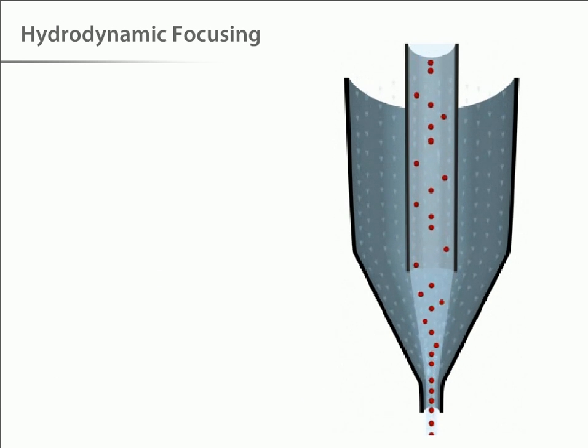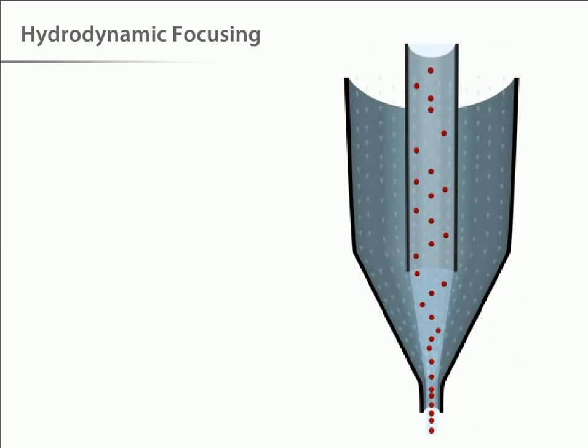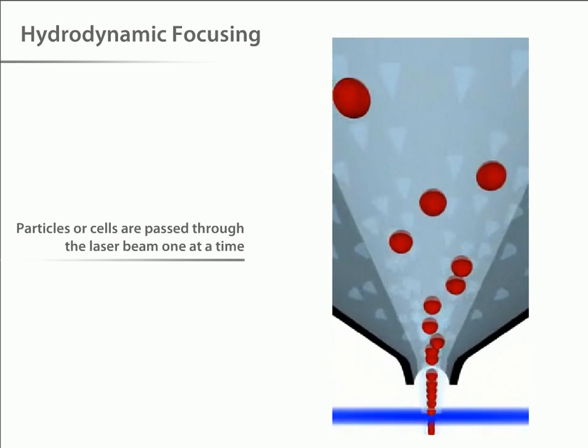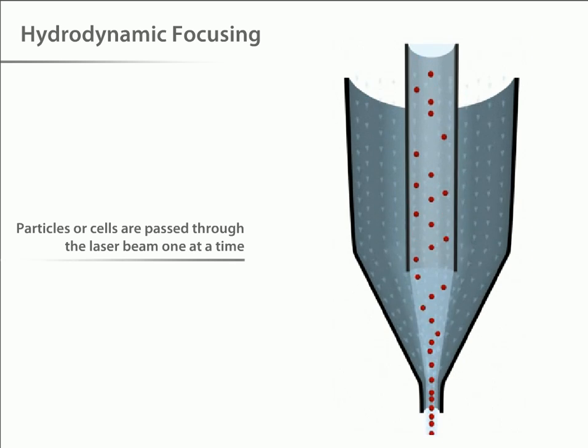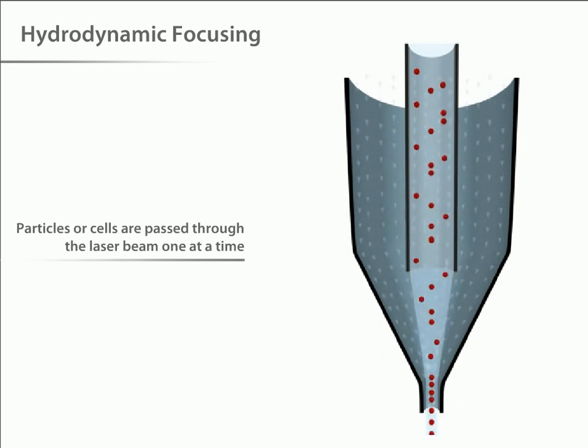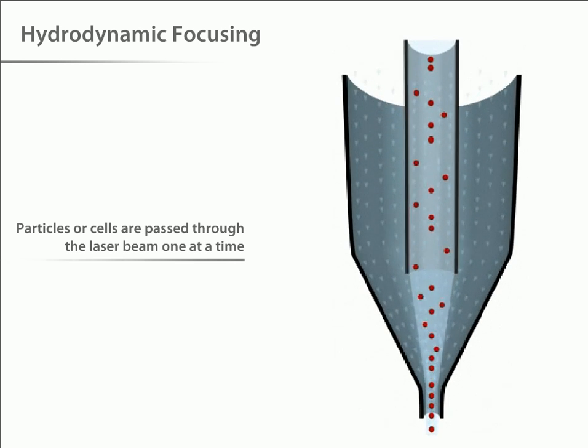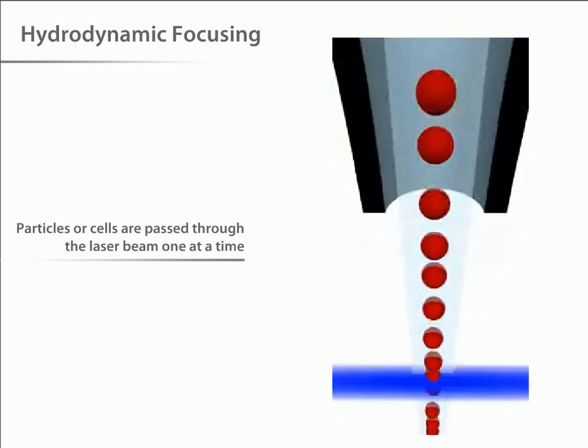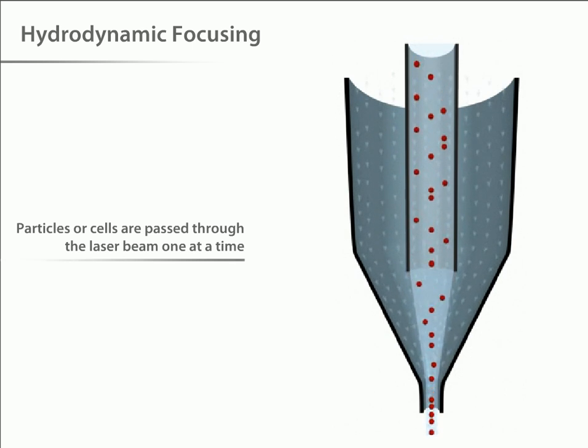Here we see how the sample is transported through the interrogation point. For accurate data collection, it is important that particles or cells are passed through the laser beam one at a time. Most flow cytometers accomplish this by injecting the sample stream containing the cells into a flowing stream of sheath fluid or saline solution. As you can see, the sample stream becomes compressed to roughly one cell in diameter. This is called hydrodynamic focusing.